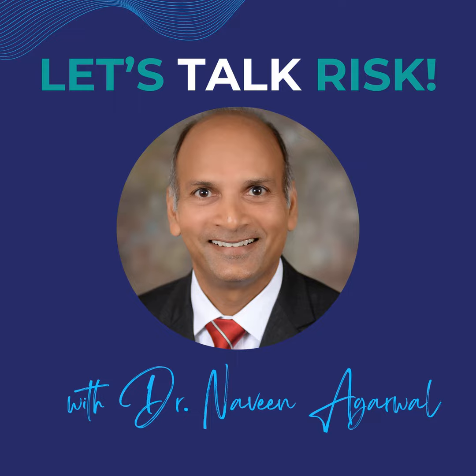be much more consistent in asking for the human factors data because of the risks associated with the user needing to understand when and when not to trust that automation and how to make decisions based on it. And what I'm even seeing is a lot of these products are going through de novo. And what's happening is human factors considerations are specifically being called out as special controls. You are right. So when they're identified and codified.